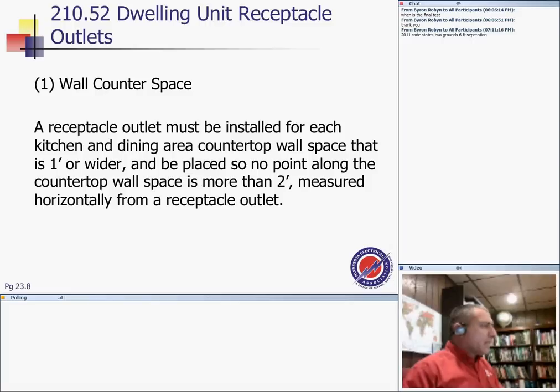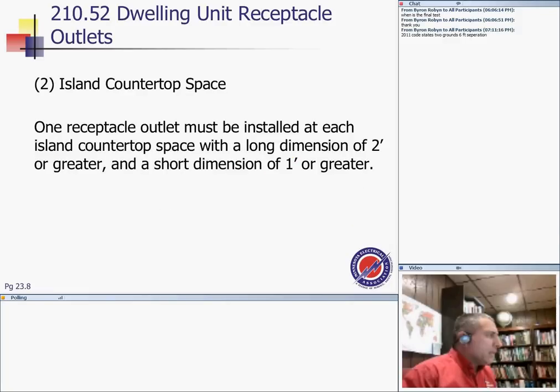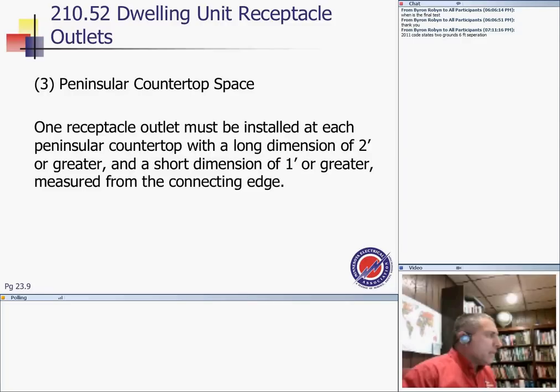One thing, here are the receptacles. Remember that 12 inches by 24 inches, 1 by 2. If you have a kitchen dining area space wider than 1 by 2, you need a receptacle for that one, like a peninsula. The same thing, 1 by 2 or more, you need a receptacle, which is 12 inches by 24 inches. You guys remember that we talked about the peninsula? Remember that term, 1 by 2, you need one receptacle at least.